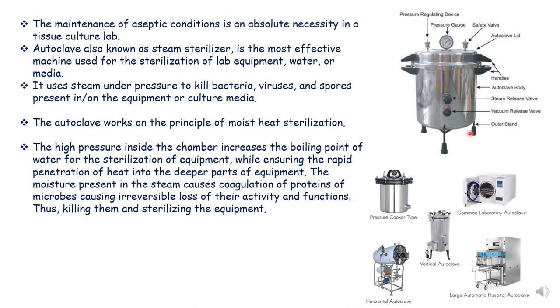In a tissue culture lab, the maintenance of aseptic conditions is absolutely necessary. The autoclave, known as a steam sterilizer, is the most effective machine for sterilization of lab equipment, water, or media. It uses steam under pressure to kill bacteria, viruses, and spores present on equipment or culture media. It works on the principle of moist heat sterilization. The high pressure inside the chamber increases the boiling point of water, ensuring rapid penetration of heat into deeper parts of equipment.